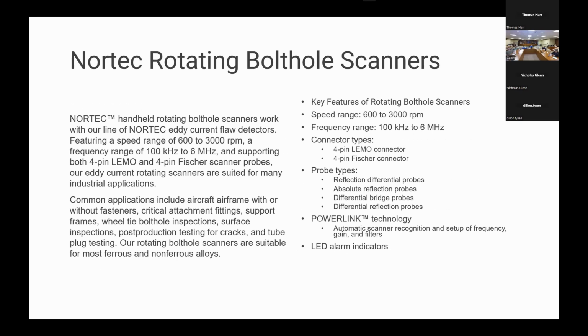One of the accessories you can purchase with the Nortec 600 is our line of rotating bolt hole scanners. These work with our line of Nortec eddy current flaw detectors. They feature a speed range of 600 to 3,000 RPM, a frequency range of 100 kilohertz to 6 megahertz, and support both 4-pin LEMO and 4-pin Fischer scanner probes.